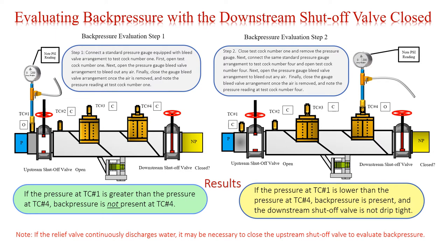Evaluating back pressure with the downstream shutoff valve closed. Back pressure evaluation step one: connect a standard pressure gauge equipped with a bleed valve arrangement to test cock number one. Open test cock number one. Next, open the pressure gauge bleed valve arrangement to bleed out any air. Finally, close the gauge bleed valve arrangement once the air is removed and note the pressure reading at test cock number one. Back pressure evaluation step two: close test cock number two. Close test cock number one and remove the pressure gauge. Connect the same standard pressure gauge arrangement to test cock number four and open test cock number four. Open the pressure gauge bleed valve arrangement to bleed out any air. Close the gauge bleed valve arrangement once the air is removed and note the pressure reading at test cock number four.